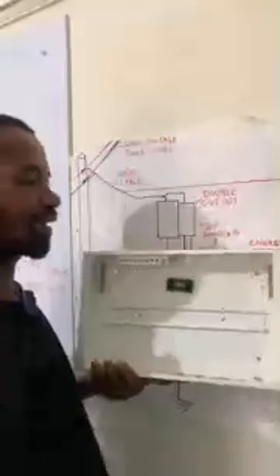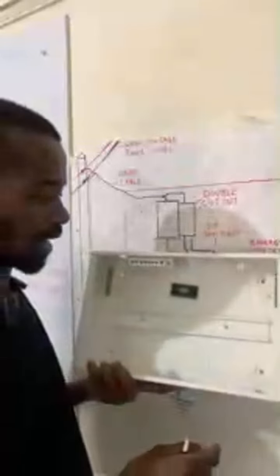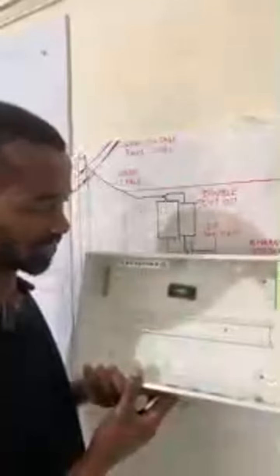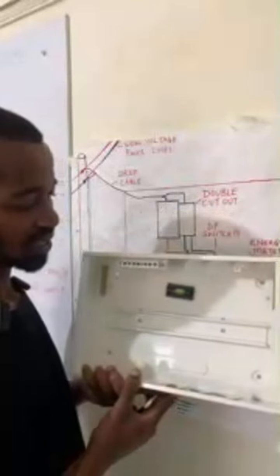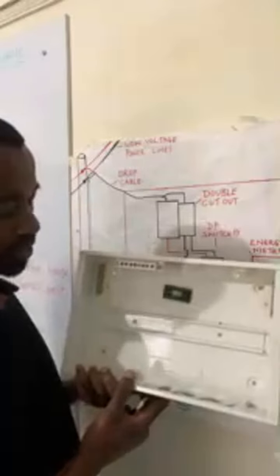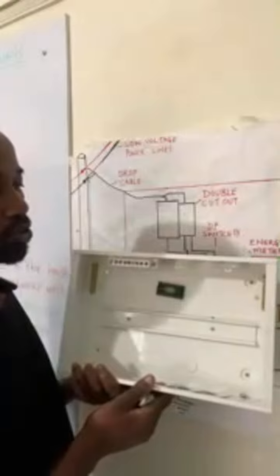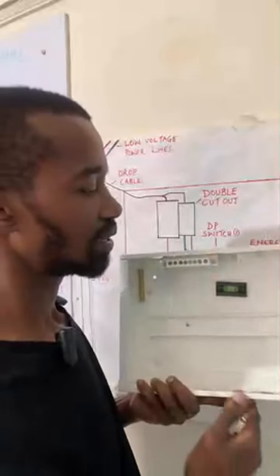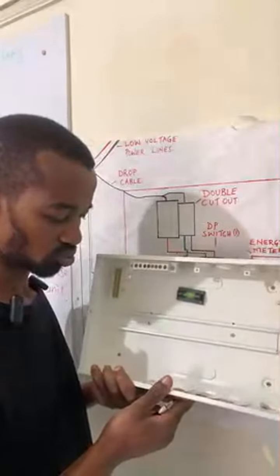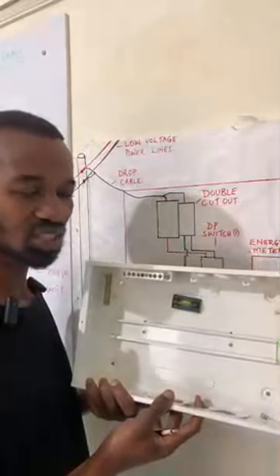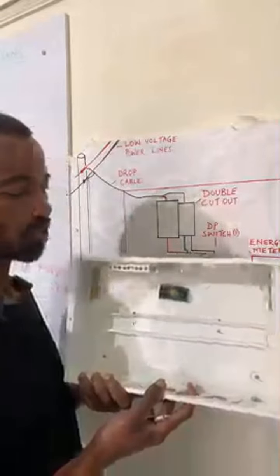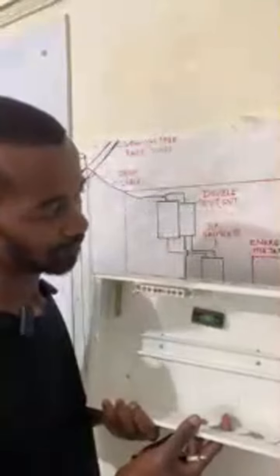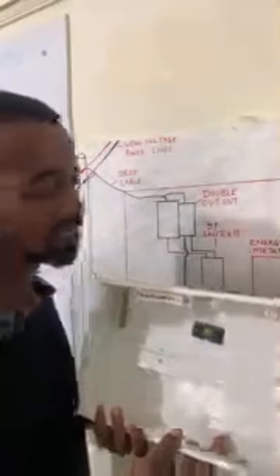So any wiring, any circuit has to return to the consumer unit. Now at the consumer unit, assuming that there are any faults, or excessive charges from the kitchen or any heating up, some of the devices in our homes or in a business setup are prone to these issues. So, for instance, when you are cooking, there are high chances that you can experience an electric shock if that appliance, let's say a cooker, is faulty inside, and therefore, if it is faulty, excessive charges will find their way to the metallic case.